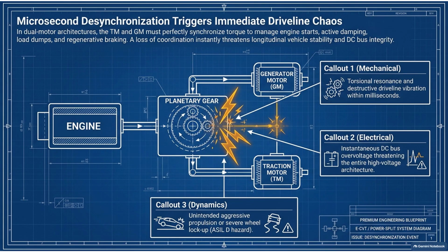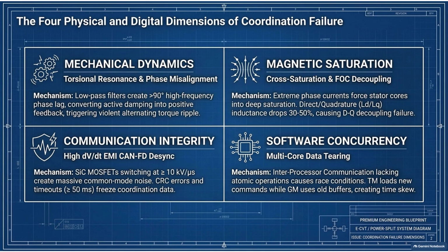But the critical failure mode here happens in the phase compensator of that damping algorithm. Mm-hmm. If the software calculation lags behind the real-world mechanical state by more than 90 degrees... Uh-oh. Yeah, your negative feedback vector mathematically inverts. Because at that point, you aren't pushing against the vibration to cancel it out anymore. Your damping pulse arrives so late that you're pushing in the exact same direction as the shaft's natural rebound. You're creating positive feedback. Exactly. You push the swing at the exact wrong time, and the swing goes completely out of control. You're injecting these high-frequency torque ripples that multiply the mechanical resonance instead of stopping it. And then the transmission enters a state of violent, amplifying oscillation.